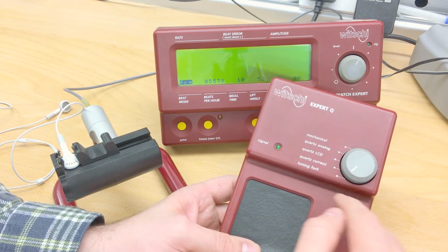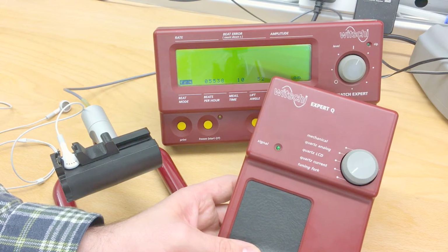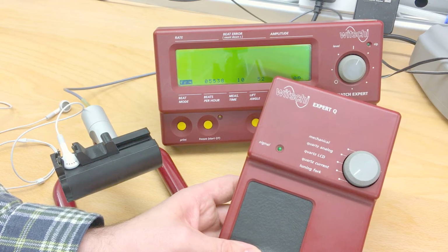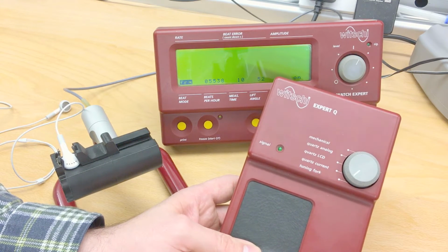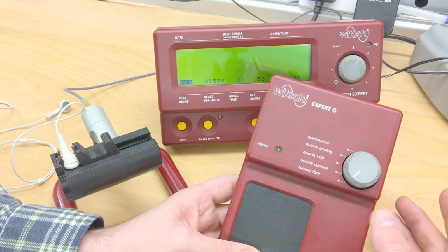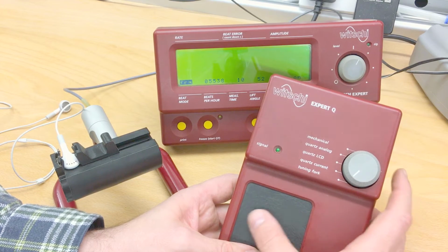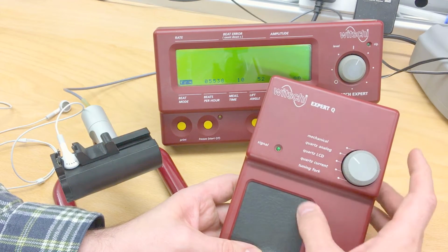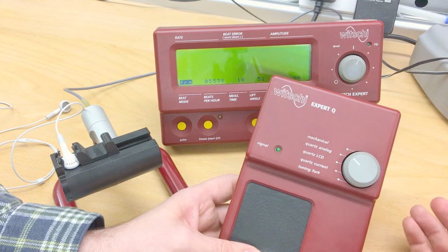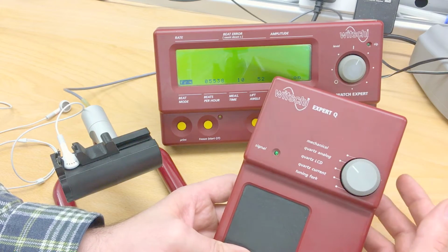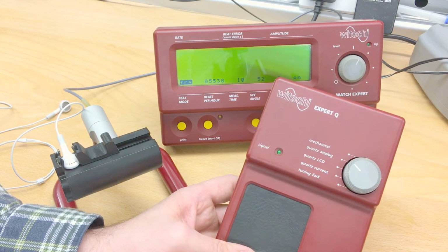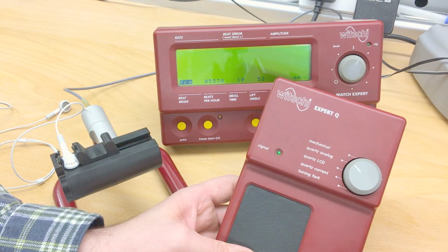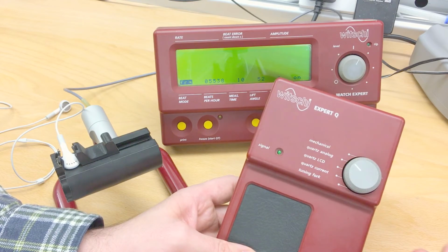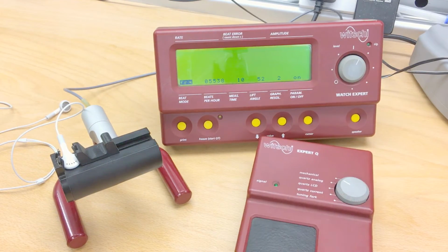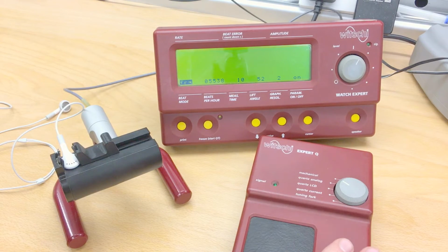And then tuning fork. So again, with tuning fork, you've got coils that really output a sine wave at 360 hertz or 720 hertz for most typical tuning fork watches. So I presume that this is just changing the sensitivity and the gain, perhaps, of the built-in amplifiers, so that the output is always at the same level. Because for tuning fork you might need much stronger gain than, for example, a quartz analog watch, which has a pretty chunky electromagnetic field. And so, as I say, I was thinking, well, I'm a bit defeated if I have got to use this to input my 1 pulse per second.